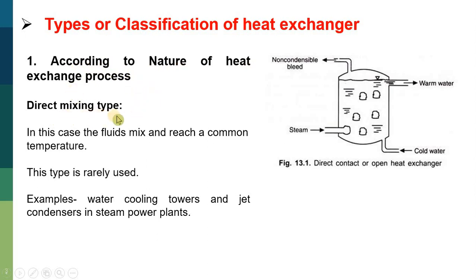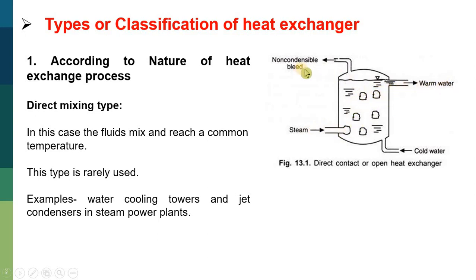Number one is called the direct mixing type. In this type of heat exchanger, fluids mix and reach a common temperature. In this diagram we observe a direct contact or open heat exchanger in which steam from a steam power plant is directly mixed with cold water. When the two fluids mix, they attain an equilibrium or common temperature. After this process the steam is converted into warm water, and any non-condensable gases are taken out in the other direction. This type of heat exchanger is rarely used. Examples are water cooling towers and jet condensers in steam power plants.